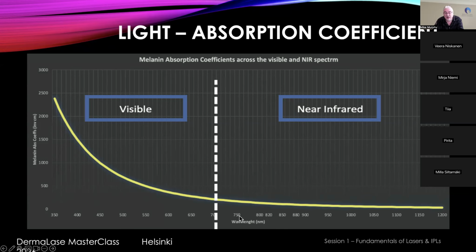And secondly, these wavelengths can penetrate quite deeply into the skin, down to the subcutis, whereas these wavelengths can't. They just can't get down there. So if you want to get deep hair follicles and heat them up, firing these wavelengths is a waste of time. They just won't do it. This wavelength range between 500 and 600 is strongly absorbed by hemoglobin.